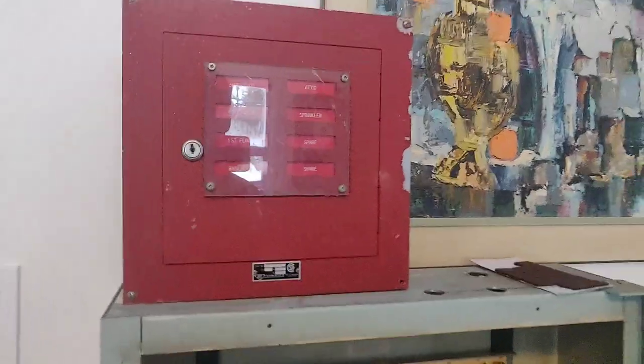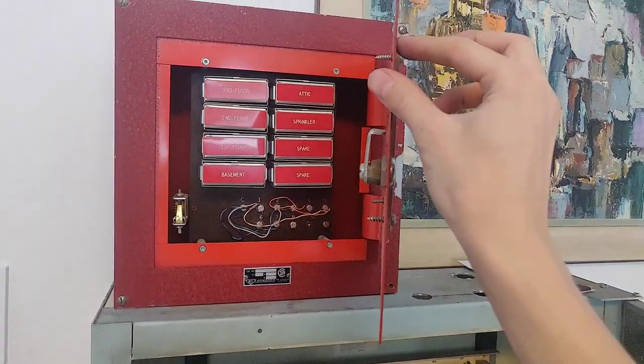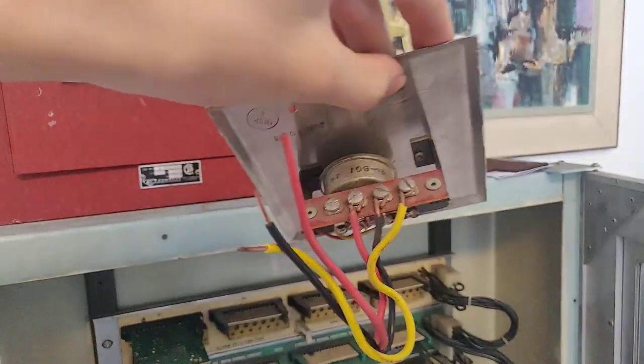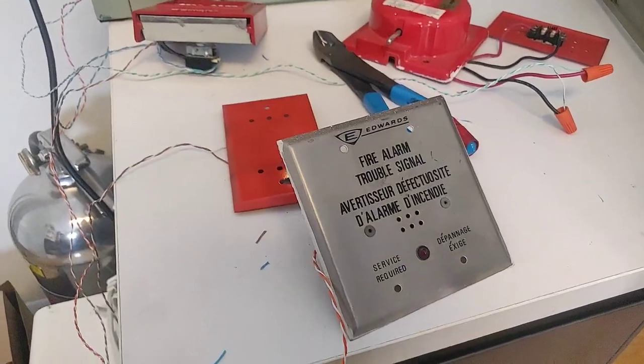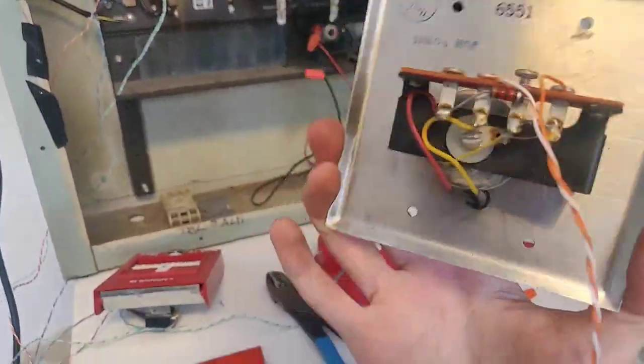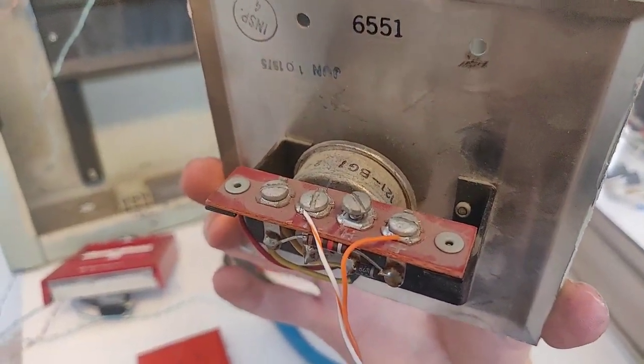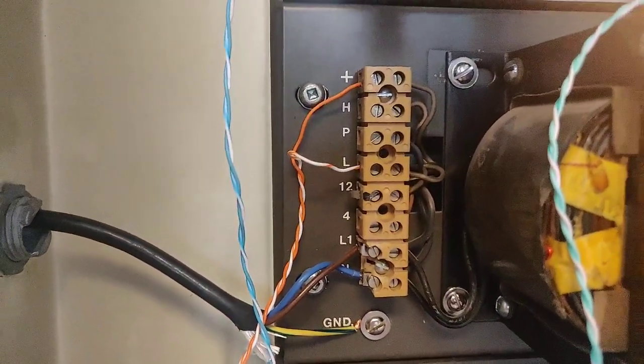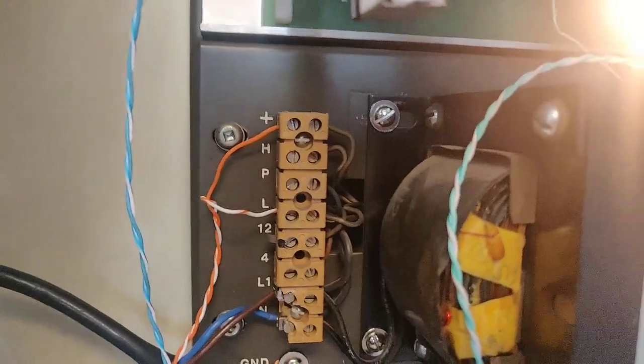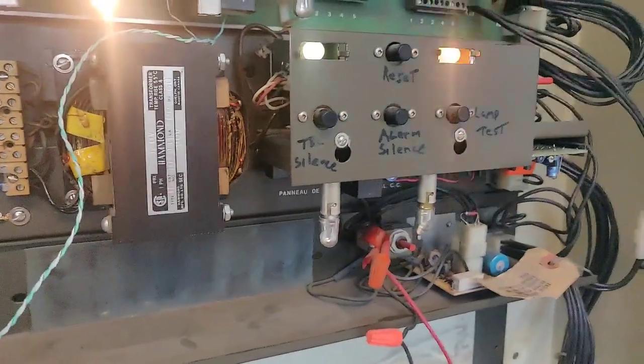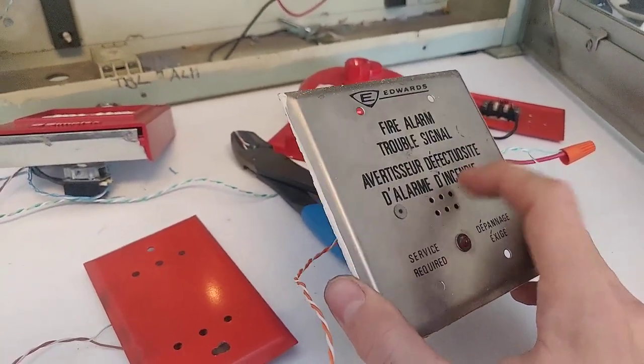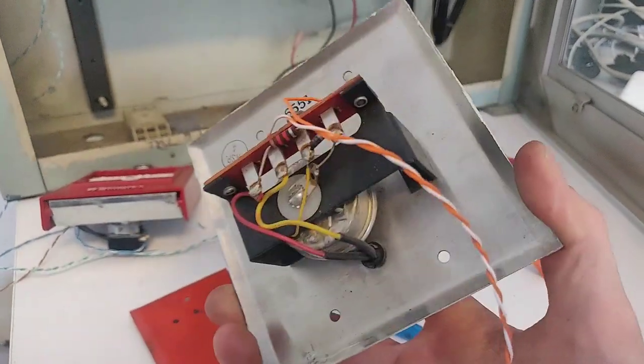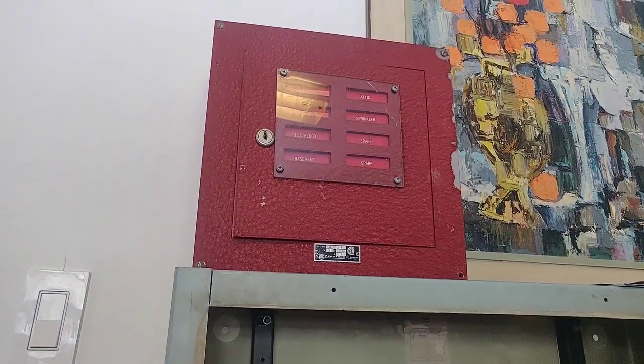So now we can get to the more complex part which is our annunciation devices. So for one we have the actual annunciator. Along with that we have to hook up this trouble signal, which is kind of interesting because it has three connections that we have to make. So if we look at this here you can see the light blinks at the same rate as the trouble light in the panel. And that's with the wires hooked up between the plus and the L. So plus meaning positive and then L grounds it out. And the H—if you connect that one you will get horn. I chose not to because it's very loud. But if you hook that up it allows you to use the audible silence for the trouble in the panel to also silence this. You'll see in almost every building that has one of these there will be like an inch of tape over this little buzzer. This thing is extremely loud—it could make a fire alarm on its own. But that's how that goes.